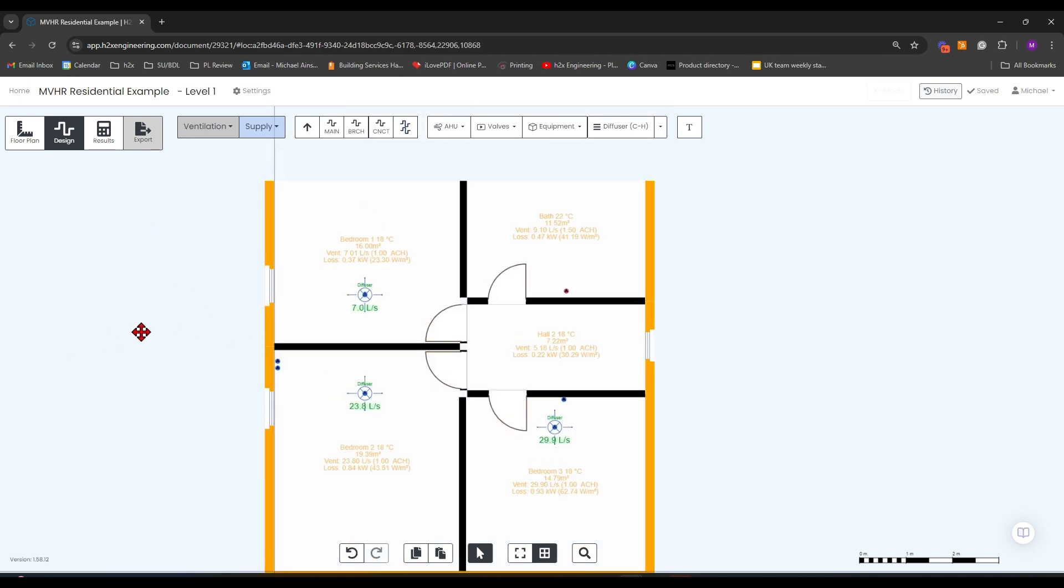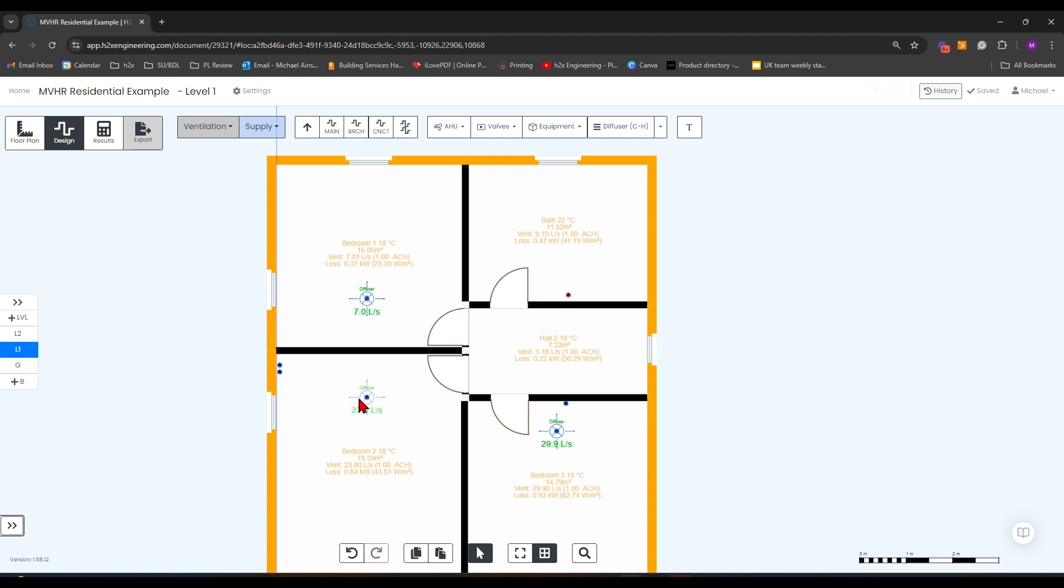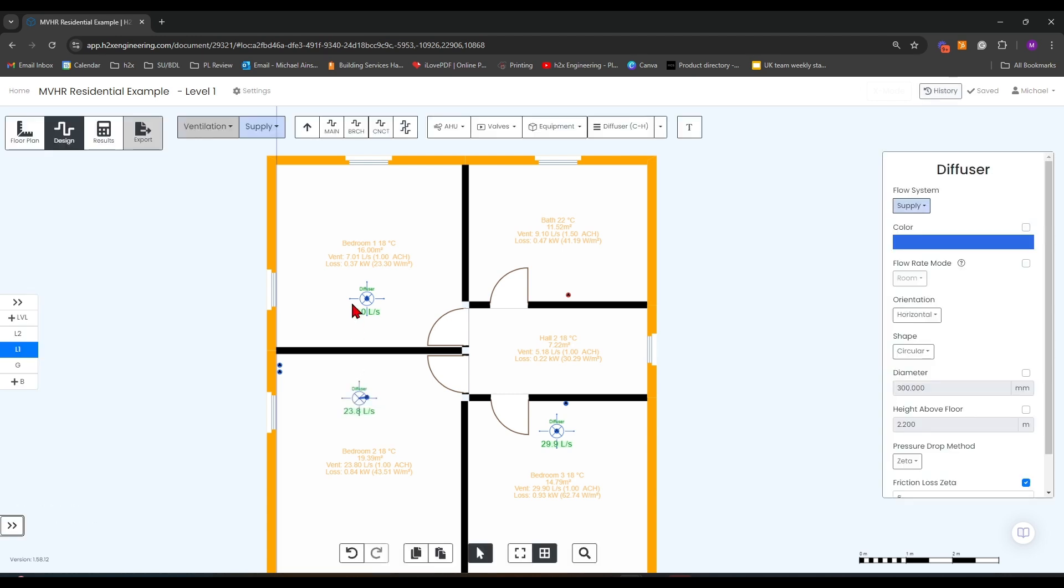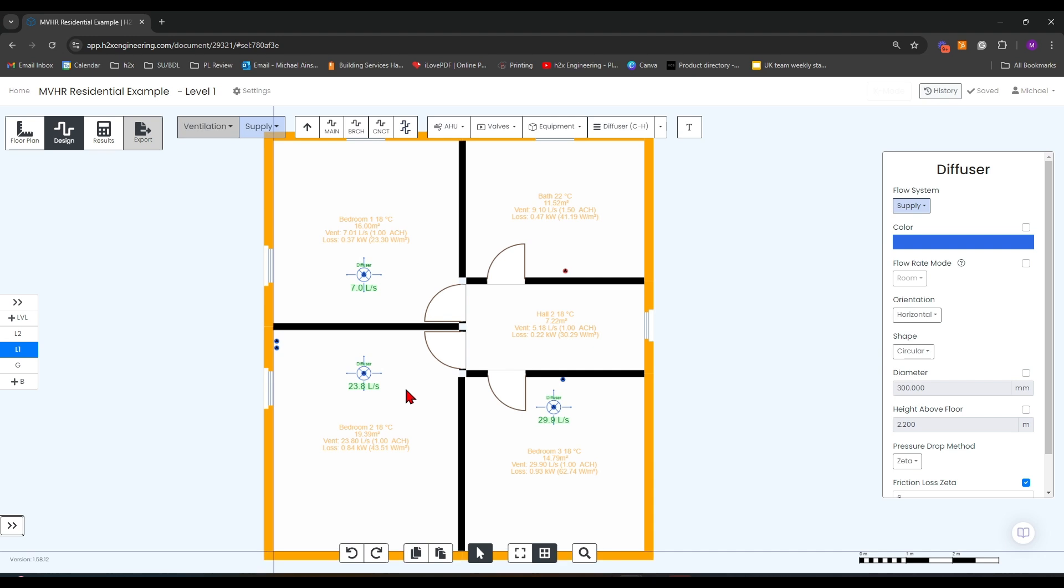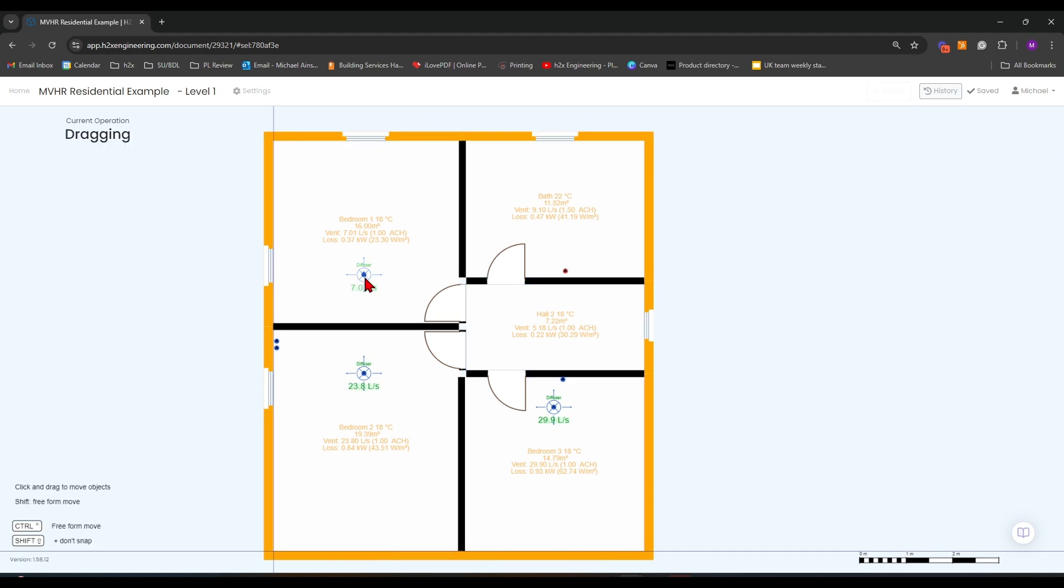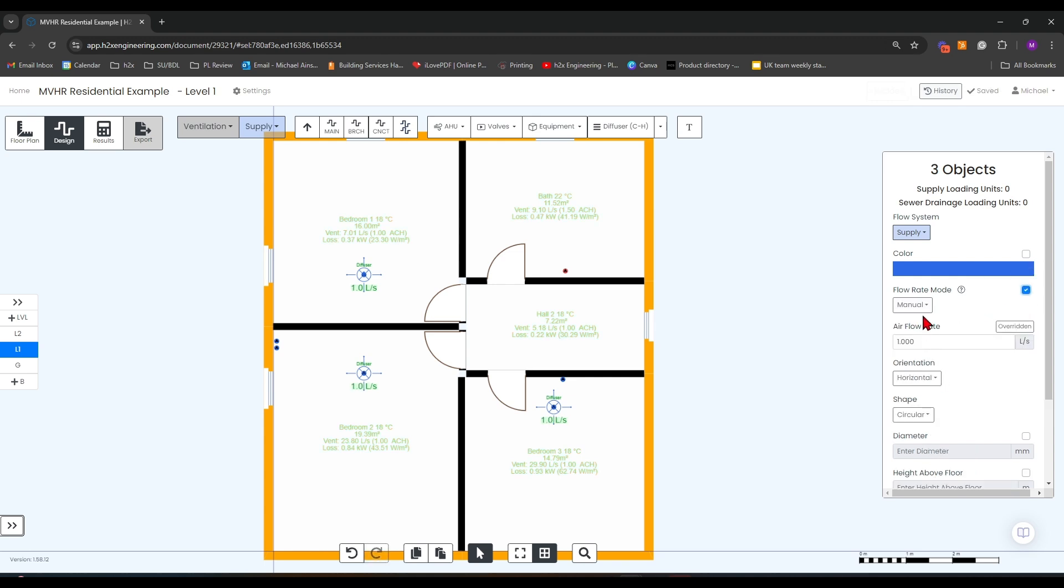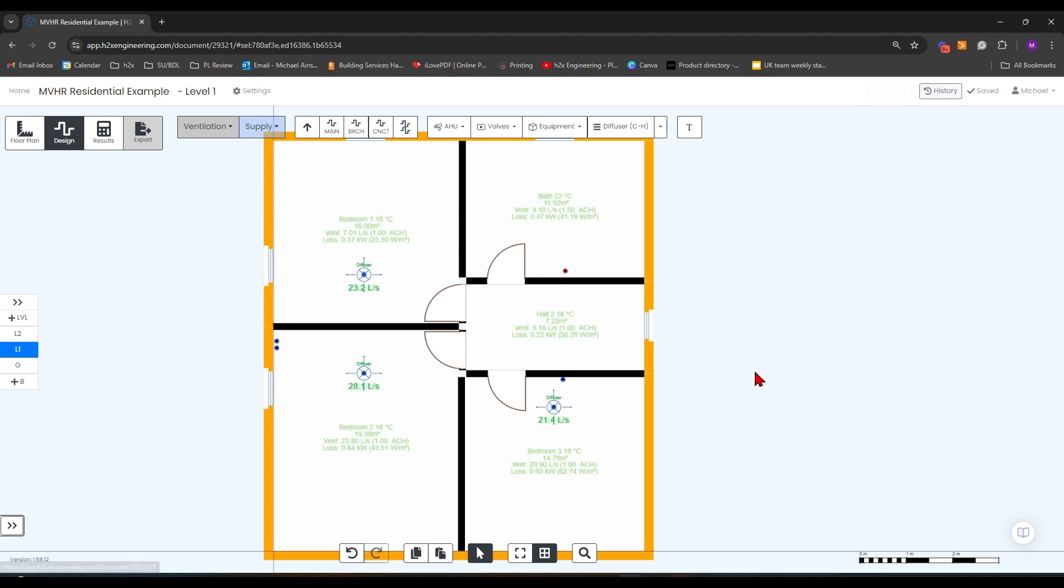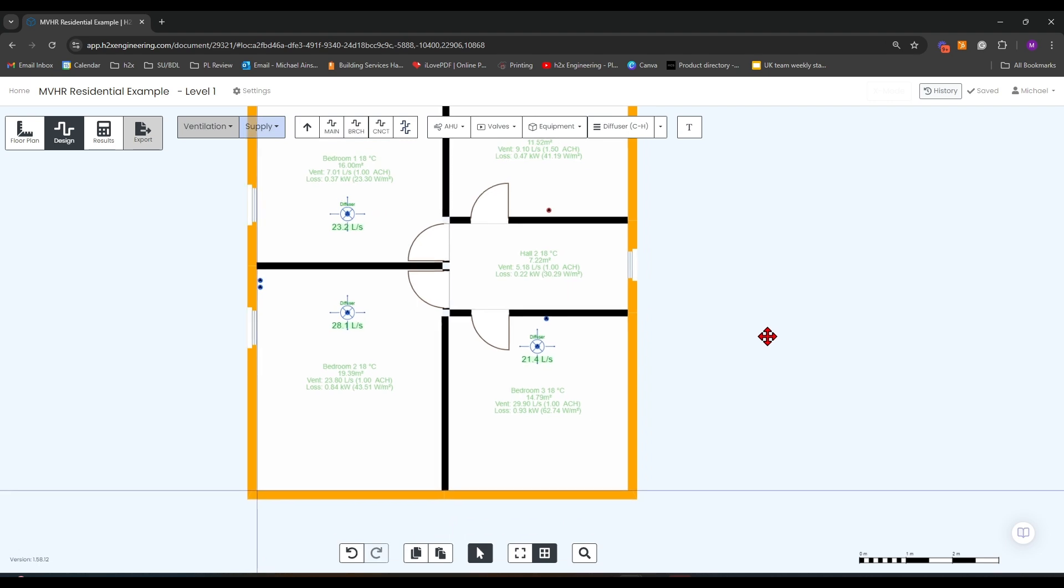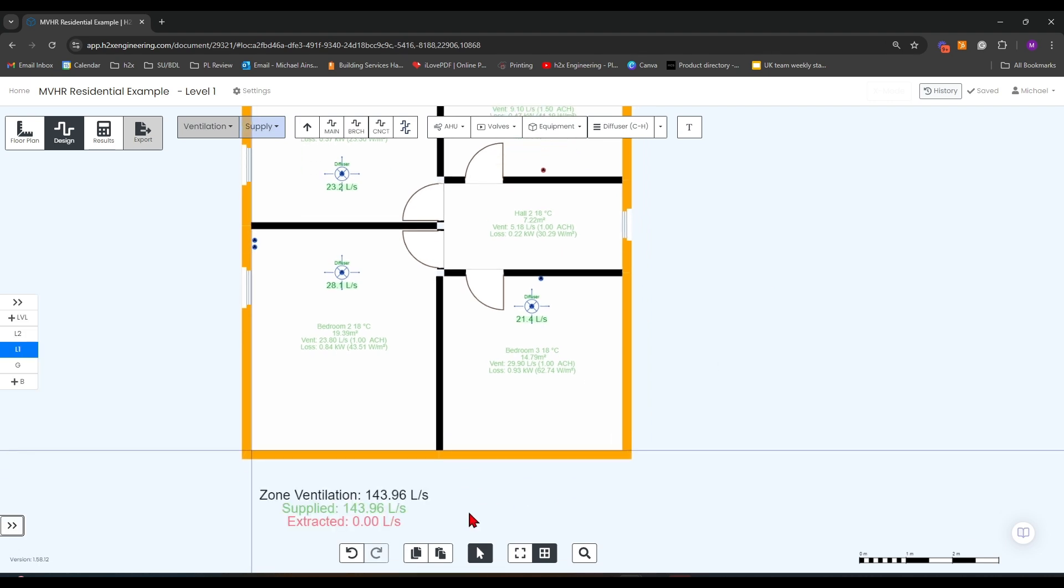This will distribute the amount of ventilation required for the property and split it by their individual sizes. For this to work properly, it needs to be done on all of the rooms. If I do this on all of the rooms, it will meet the requirements of the entire building. If we go to the ground floor, you can see that our supplied ventilation has turned green.